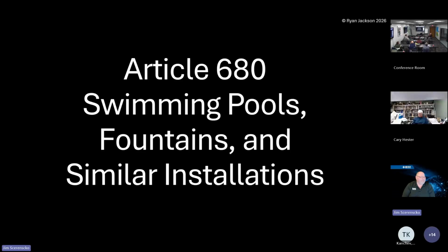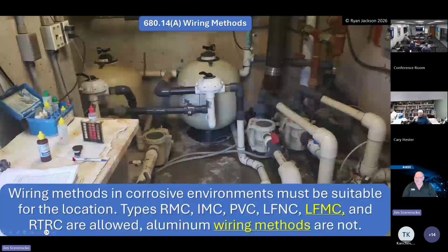Swimming pools always get everybody; everyone always sweats bullets over swimming pools. There was a definition change, you saw that. There's that issue about the corrosive environments and what wiring methods can be used in the corrosive environments. So they added liquid-tight flexible metallic conduit in there. So it used to be just liquid-tight flexible nonmetallic, but now it's metallic as well. So basically Carflex and Sealtite, which are trade names that we're more familiar with. Pool rooms are notorious for being just bad.